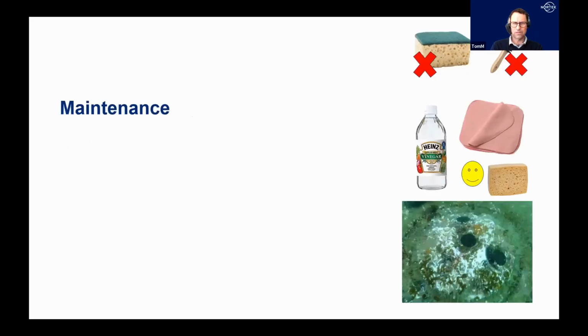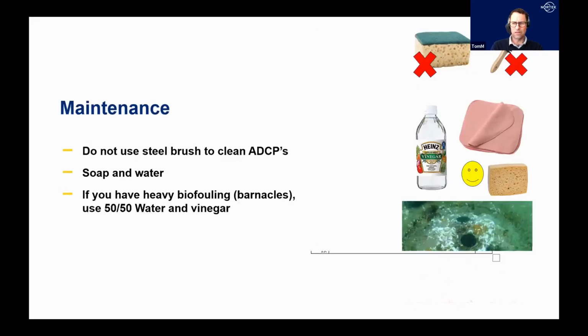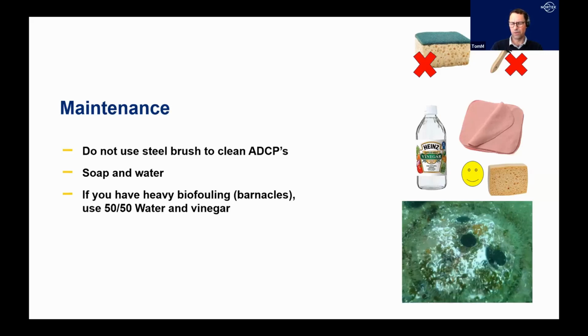Another thing is maintenance. We do see instruments coming into Nortek in Norway for service that have been cleaned with steel brushes and sponges with hard surfaces. Please don't do that. If you've experienced a lot of biofouling, I usually go for a 50-50 mix of vinegar and water in a bucket, and just leave the instrument there for a day or two - it will be really easy to clean up afterward.